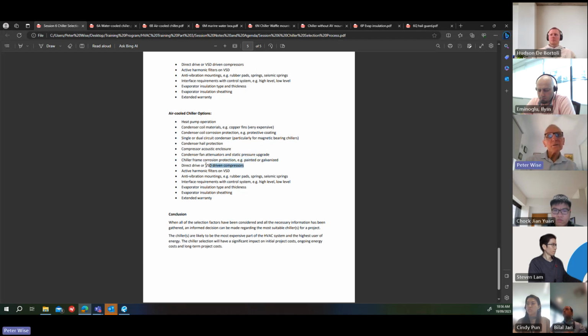Direct drive or VSD driven compressors again. So these are the same sorts of options now as water-cooled. Active harmonic filters on the VSDs. Anti-vibration mountings. Now the air-cooled chillers will normally be installed on the roof. So you might need to think about vibration isolation in this case, if it's a tall building. So again, rubber pads might suffice, or springs or seismic springs.